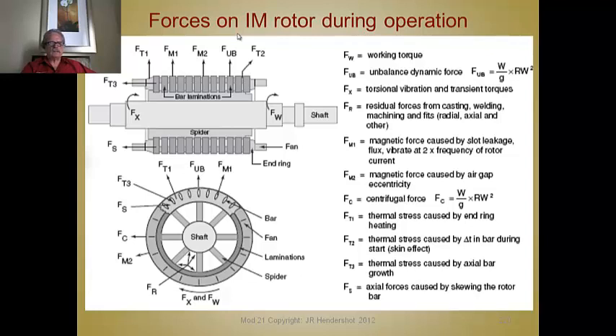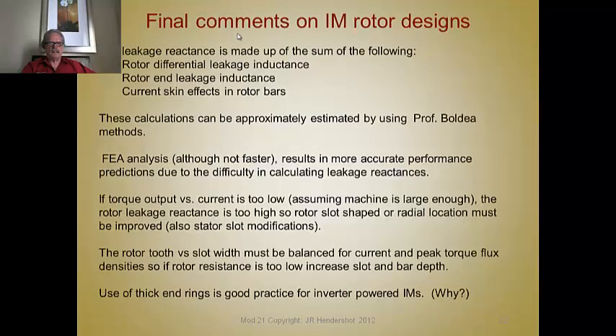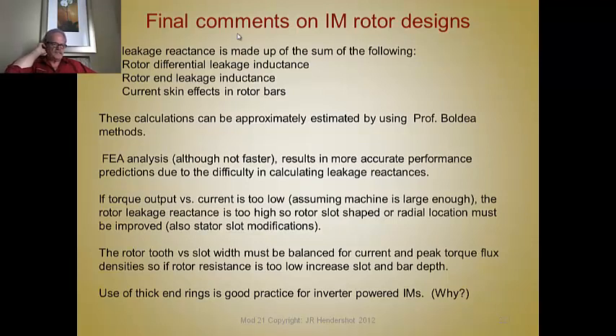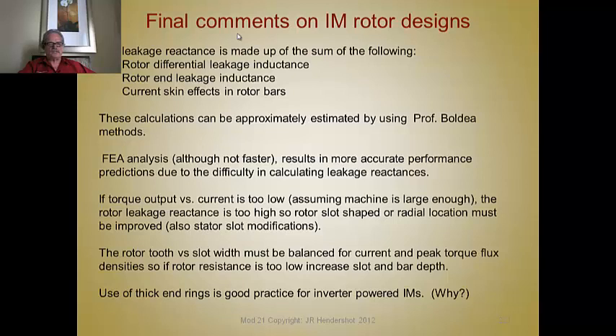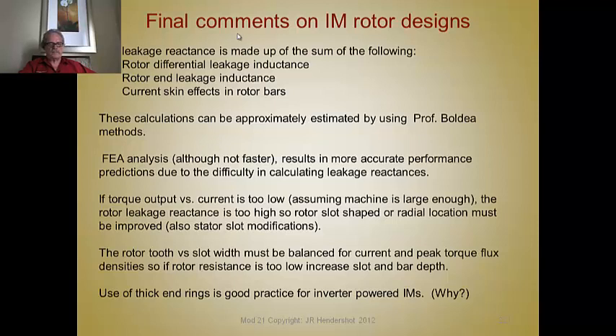Here's a summary of all the forces on a rotor — worth analysis and study by your mechanical engineer counterparts. For final comments on rotor design: the leakage reactance is made up of the sum of rotor differential, rotor end leakage, and current skin effect in rotor bars. These can be approximated using Professor Boldea's methods, while FEA methods result in more accurate performance predictions. If output torque versus current is too low, the rotor leakage reactance is too high — so rotor slot shaping and radial location of the bars must be improved. The rotor tooth versus slot width must be balanced to produce peak torque without excessive tooth flux density.